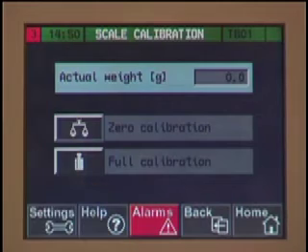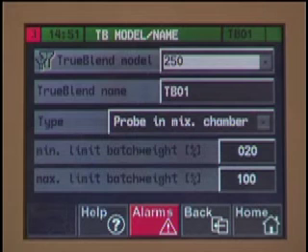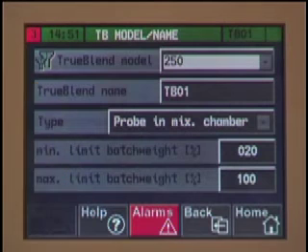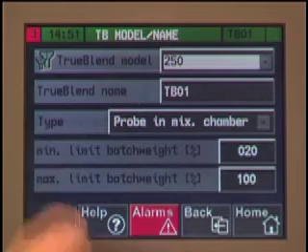Let's walk through the process of doing a zero calibration. Make sure that the weigh bin is in place and empty before proceeding. Press the icon to open the zero calibration screen — zero is displayed for actual weight. True Blend model name is the next setting below scale calibration; this allows you to choose or change the blender type, most frequently used when setting up a spare or replacement control. The True Blend name allows you to uniquely name the blender for plant identification. Limits allows you to set minimum and maximum batch weight percent. The last screen under the settings screen is batch mode, which sets a target weight to fill a drum or gaylord. In normal operation, the blender will continue to make individual blended batches of material until the mixing chamber level sensor is satisfied or the blender is turned off.